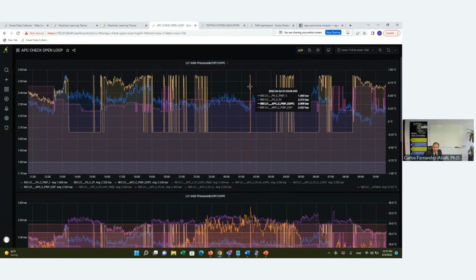And that's what you can see here in these jumps in set points, okay, when the prediction has departed from the high limit. This is an open loop optimization, so it's an open loop graph. So your blue line is your process variable, your yellow line, sorry, is your cyclic COP set point, and your purple line is your actual COP set point. And as you can see, sometimes you can gain improvements and sometimes you can't. Sometimes you cannot rise. And the system is saying, actually, to behave optimally, you have to come down to the purple line and spend more energy.